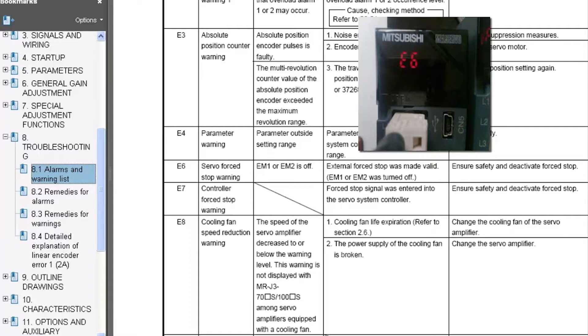Not every amplifier is going to allow you to disable the E6 warning through software. For example, the MRJ3-A amplifiers, the analog type amplifiers, are not going to allow you to disable that warning.